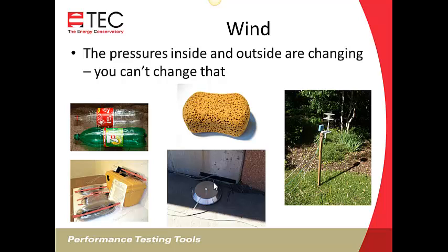Gary Nelson, the owner of the Energy Conservatory, has done some extensive testing where he's graphed things for days on end in all different types of scenarios, putting different types of measuring devices next to each other. One was even a sprinkler soaker hose spread out over a large area with a tube connected to that. None of these things really seemed to matter very much. The one that worked the best, that was most repeatable, if you're just using a single tube, was to do like is done on this lower one, where you're running a tube close to the house, in the center of the house, on the side of the house away from the wind. That always seemed to be the best position, where you get the most stable readings.